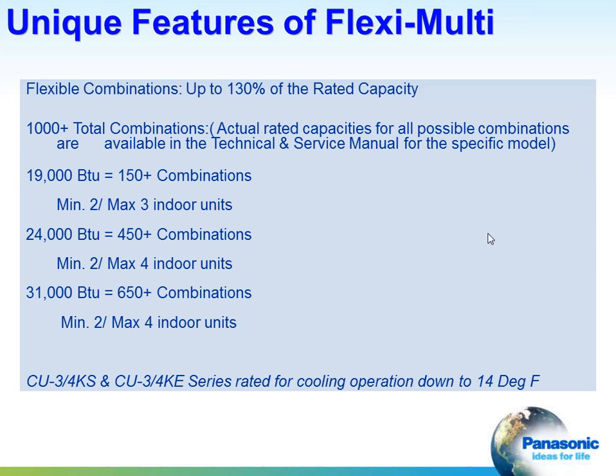And just to give an indication of the many different combinations for the 1.5 ton, there's about 150 different combinations. And with all these systems, you have to use a minimum of 2 indoor units. So for that 1.5 ton, minimum of 2, and you can go up to 3 indoor units. The 24,000 and 31,000 BTU systems, you can have a minimum of 2 indoor units and a maximum of 4. And again, these are meant for regular space cooling and heating. Cooling operation is only down to 14 degrees.